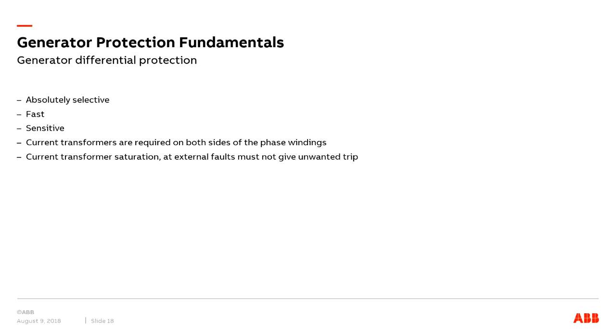Differential protection will trip instantaneously for all internal faults, as there is no need for delay to achieve selectivity. Also, the generator differential protection will be able to detect fault currents much smaller than the generator current at normal operation, giving good sensitivity. As I mentioned, the current transformers are required on both sides of the generator windings. And the generator differential must be designed so that current transformer saturation at external faults does not give unwanted trip. So that is one of the important things to be dealt with by protection engineers: how to avoid a false trip or a misoperation in the event of a CT saturation condition.